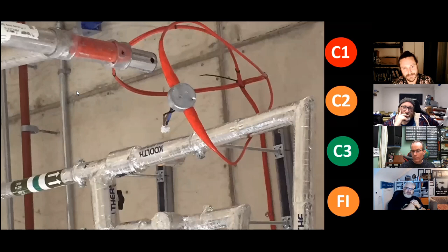The trouble is, I'm not going to lie, Dan and the lads, you go onto any commercial industrial site, you will see bodges, modifications, temporary appropriations of the fire alarm system in this manner. Plastic connector blocks inside a joint box as a temporary thing, where people might terminate the cables until there's a wall or somewhere they can dress the cables down. Because if you look at it, is that two cables there? So that may be where there's a wall supposed to go. And all they've done is coil it up in some manner, put it in a through box, connected it with the intent of a lid so that they can then start belling out the wires so they can get off site. Even though that's MICC, it looks quite new.